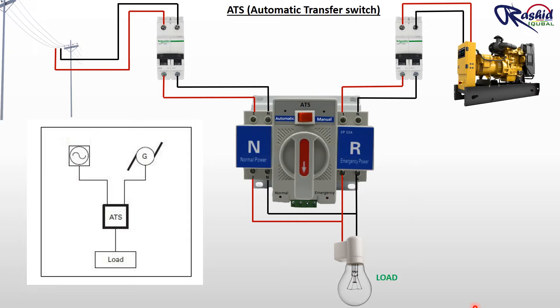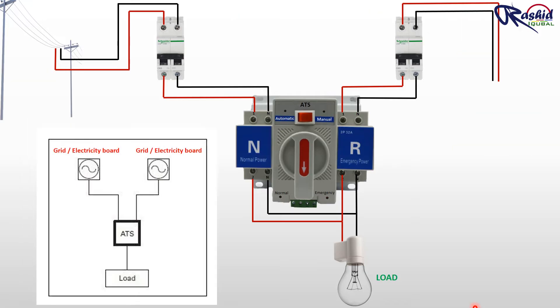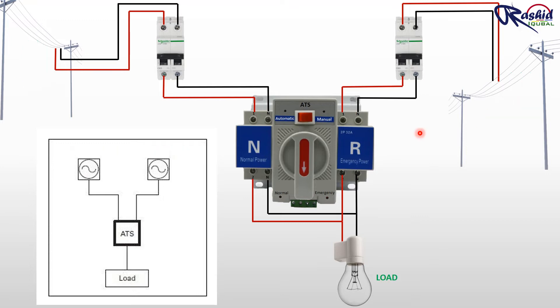In this option the primary source is connected to the electricity board and secondary source is connected to generator. On the second option, both primary and secondary source are connected to grid or electricity board. These two sources could be independent of each other, requiring the provision of two electric services by the public utility provider, or they could come from a single electric service that is distributed via redundant pathways inside the facility.